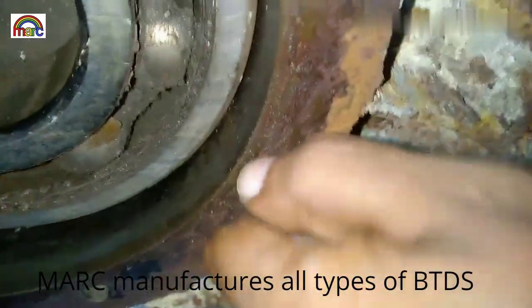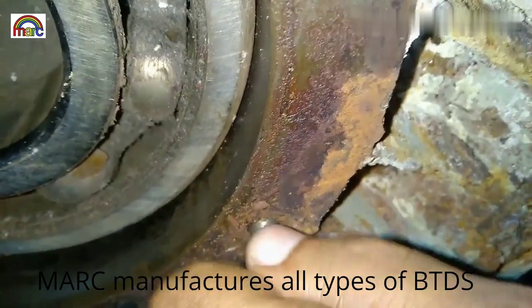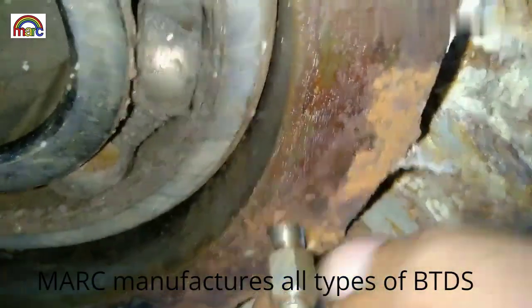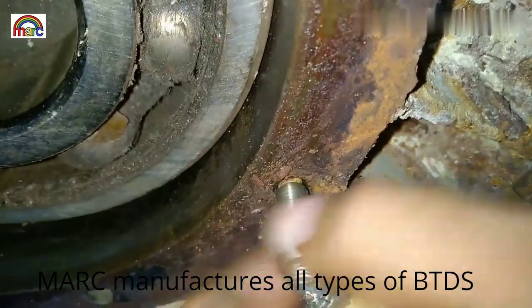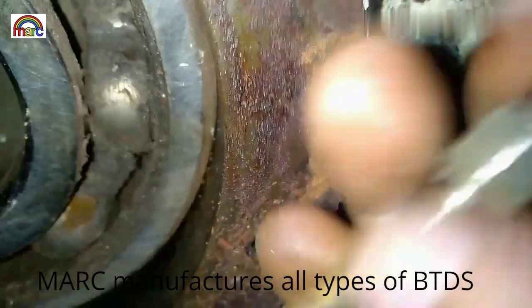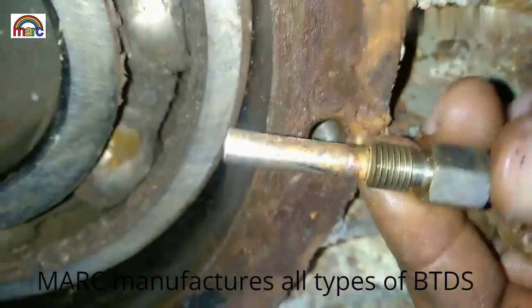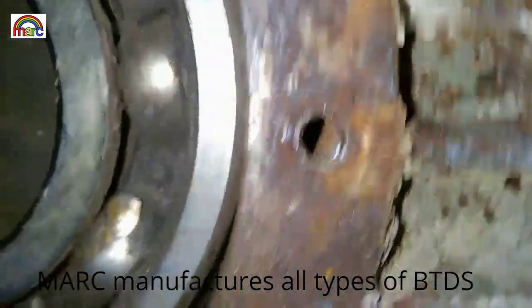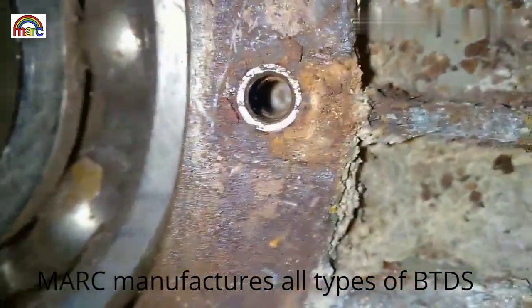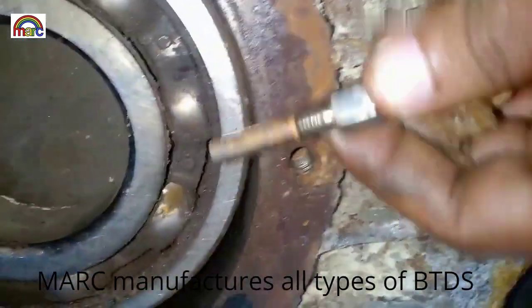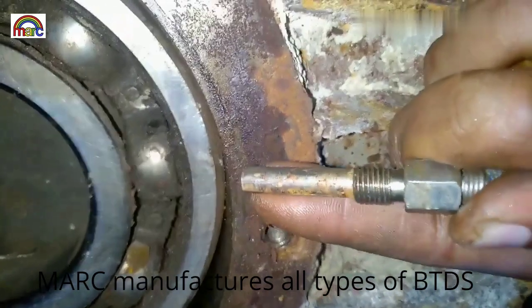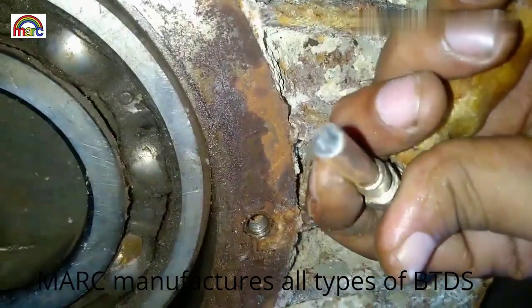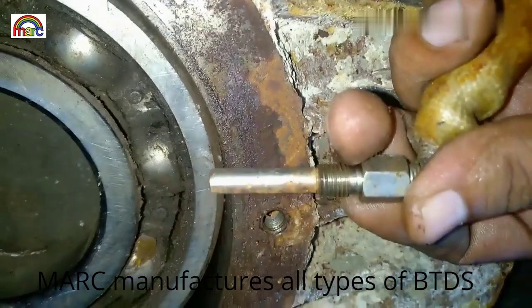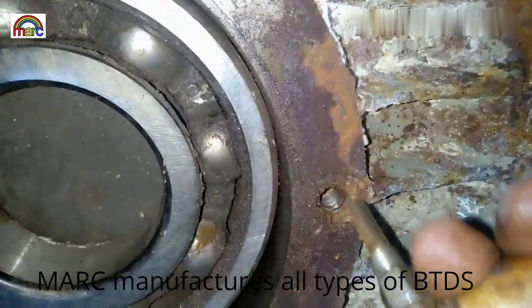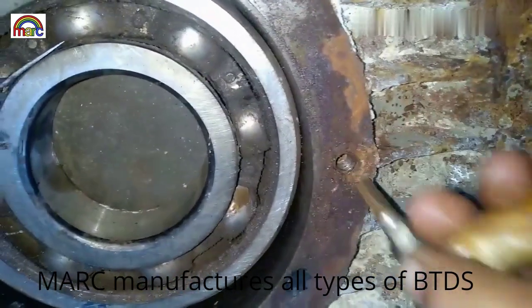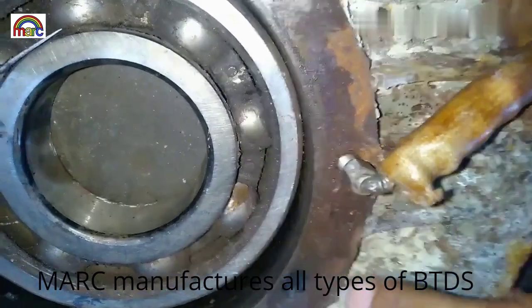Let's remove the BTD and see how it is placed. This is a bolt type BTD, meaning the probe is designed like a bolt. Here you can see this is the probe. This probe goes inside the bearing housing and is connected over there. Whatever temperature is generated by the bearing will be transferred to the end shield or the bearing housing, and from there it will be sensed by the BTD and transferred to your metering circuit. This is how the probe is assembled.